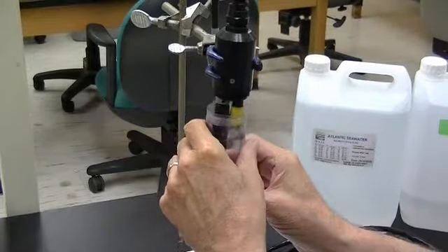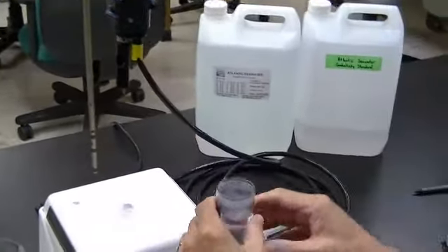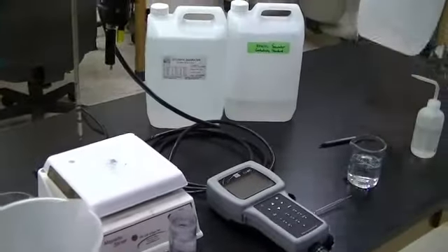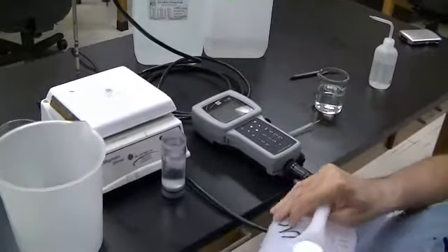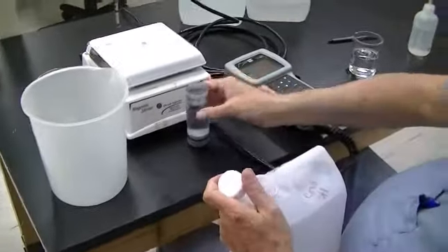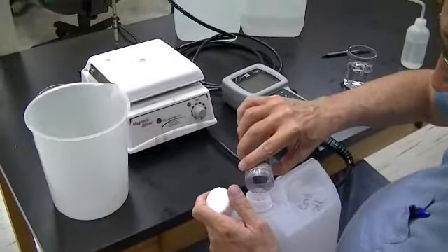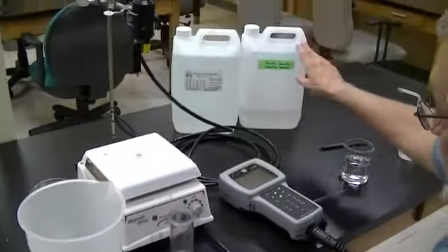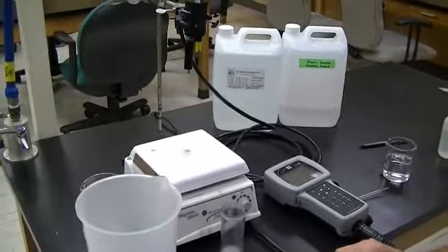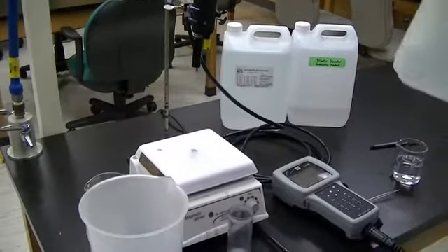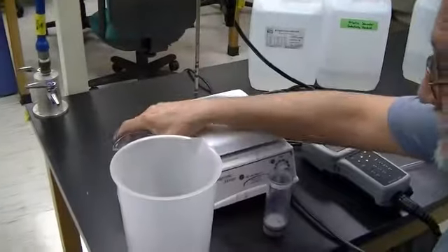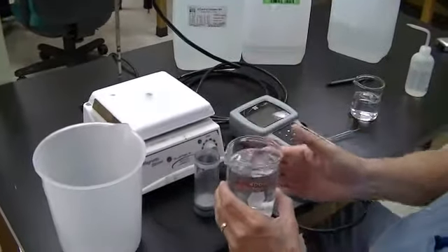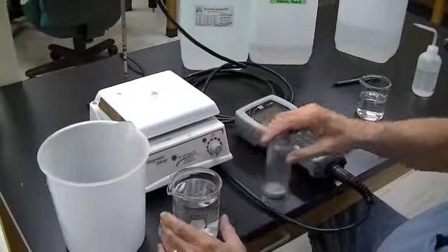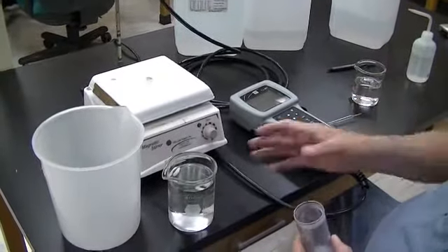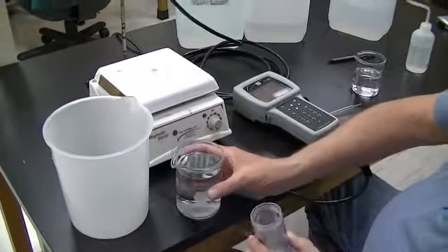So now we go back to the probe, and we take the conductivity chamber off, and we go over here and get the used conductivity standard bottle and just pour this back into the used conductivity standard. Now again, when you do it, you would use seawater from the unused conductivity standard. Okay? All right, then you take your natural seawater. Now this is just natural seawater that I got out of the basin some time ago. You would get it from a bucket, but you'd pour it from a bucket into a beaker like this, and you pour.